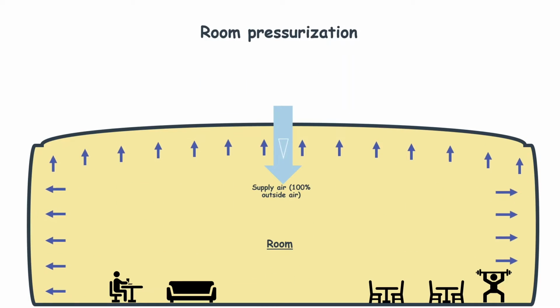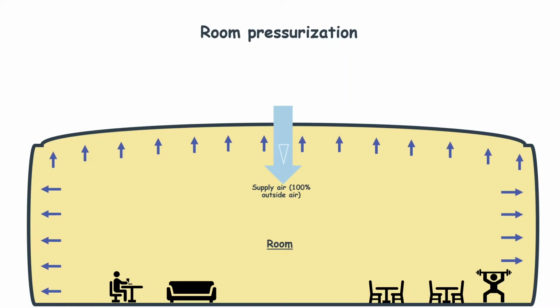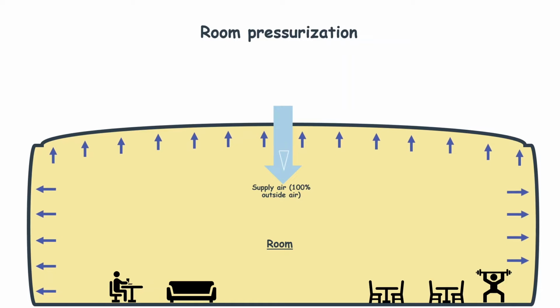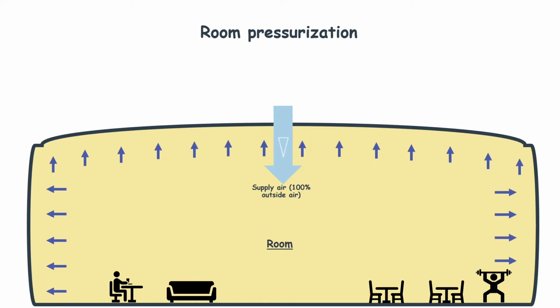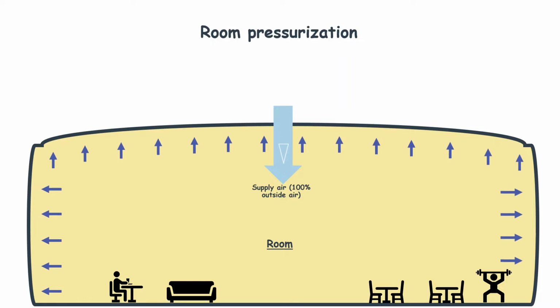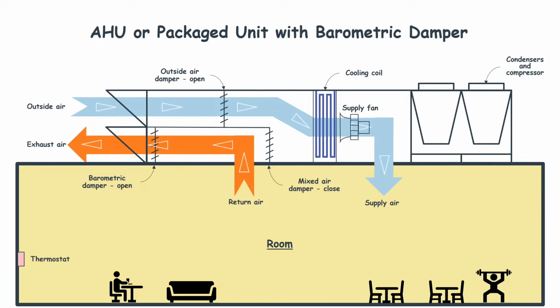As you may have guessed, by supplying 100% outside air, we are pressurizing the room, and we need to somehow relieve this extra pressure. There are three methods to relieve this extra pressure. The first one is using a relief damper. This method is mainly used for small systems. In this method, an automatic or barometric damper opens up when the system goes into the economizer mode. With this method, the room will still be at a slightly positive pressure, but this positive pressure will not cause any issues such as excessive noise in the rooms.